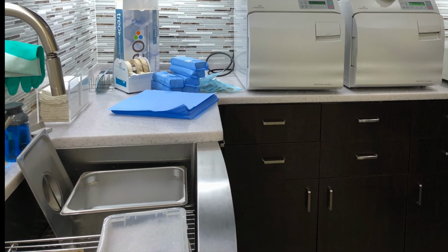But to put in the surgical milk rinse, they actually put an extra tank or an extra container in the sink. Fortunately, they had a wide sink, and they were able to put that container in, and he was able to continue to use the same ultrasonic that they had. So he was able to slide out the dry heat sterilizers and slide in 2 new gravity sterilizers with that, and meet the standard of care for wrapped packaged sterile instruments very efficiently before he reopened his office after the pandemic. So lots to consider, meeting that flow of going from dirty to clean to sterile, and sterile storage with it, but that's absolutely a requirement.